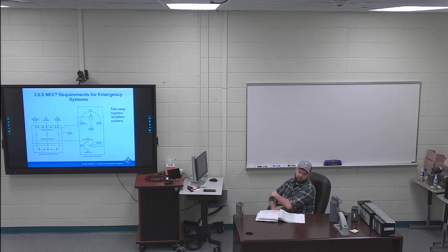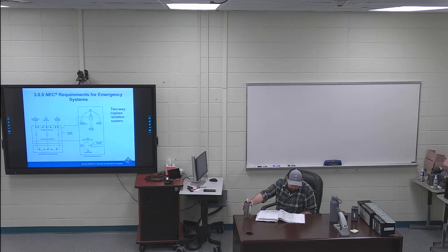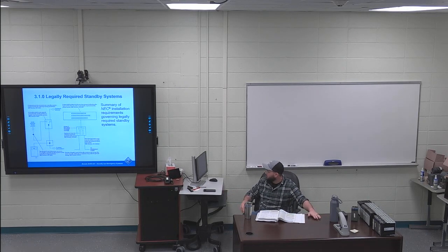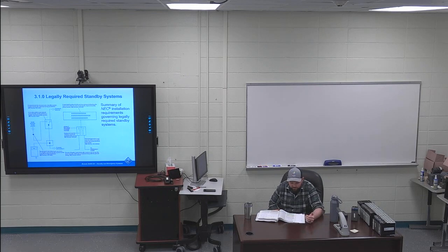Section 3, NEC requirements for emergency systems. First paragraph on page 20, second sentence. In general, NEC Article 700 deals with emergency systems. Article 700. Next section, 310, legally required standby systems. 310. First sentence is highlighted. NEC Article 701 covers installation requirements of legally required standby electrical systems. 701 is for legally required standby electrical systems.